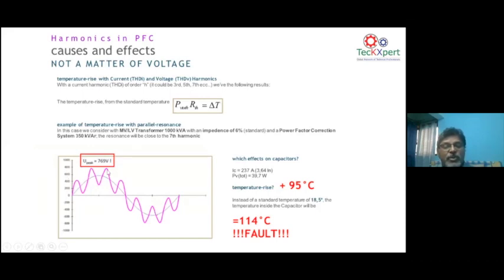A distorted waveform is there. And then you can see the temperature rises on the capacitor substantially. That means if you go and touch the casing, you will not be able to touch it, of course, because it will be more than 100 degrees. So here it is showing a conventional capacitor, which is not subjected to harmonics, working at a normal temperature. But the moment the capacitor is subjected to harmonics, you have a situation with regard to temperature rise on the capacitor.